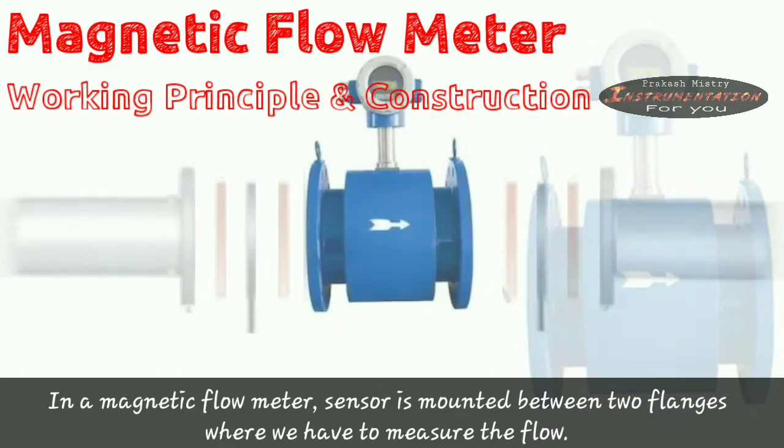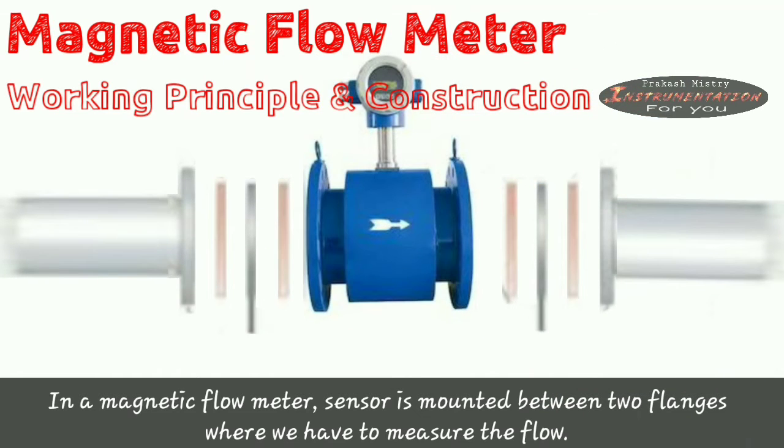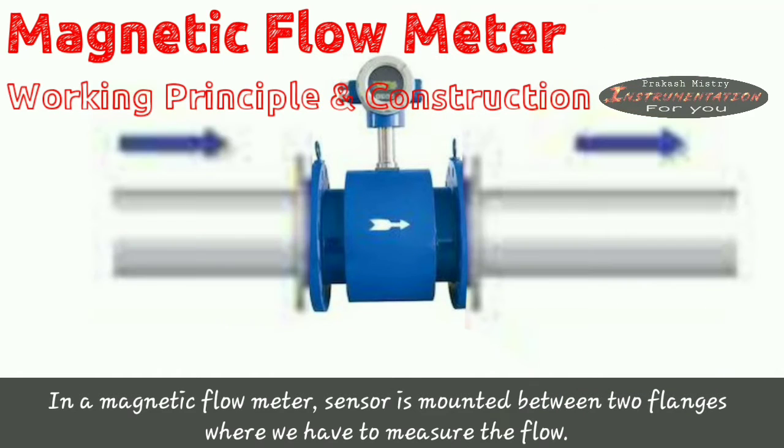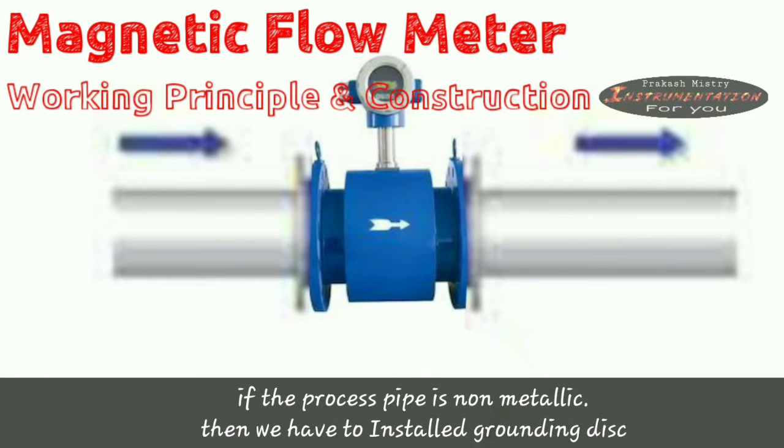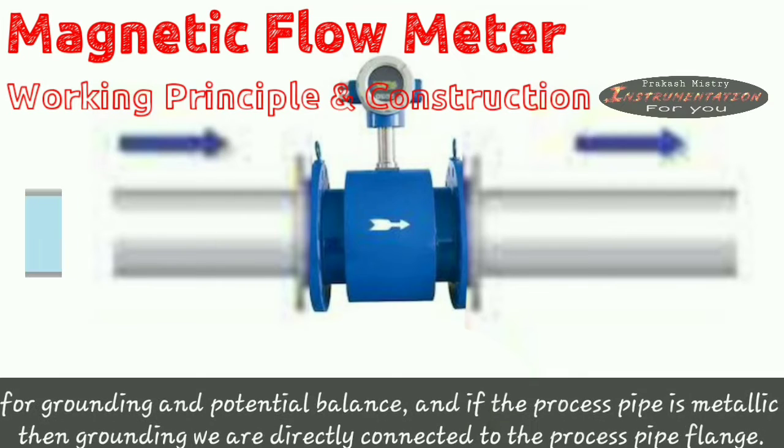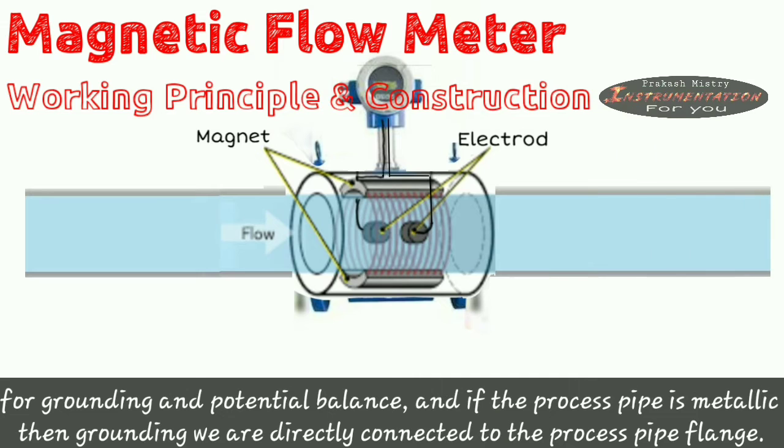In a magnetic flow meter, sensor is mounted between the two flanges where we have to measure the flow. If the process pipe is non-metallic, then we have to install grounding disk for grounding and potential balance.